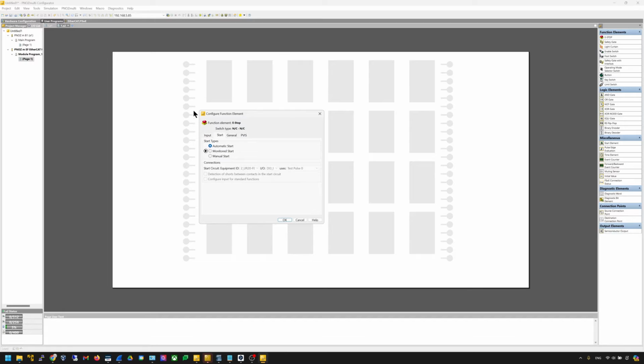Then go to start. Here is the tab to configure your e-stop signal. E-stop by control block: it should be automatic start, monitored start, or manual start. In this case, I use manual start. And for the manual start, then there are the connections. You can choose the connections. So I choose A2, and then I choose I2. It means that this A2 is a non-safety EtherCAT communication.